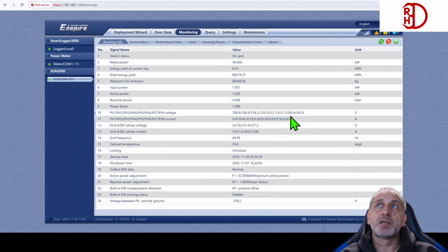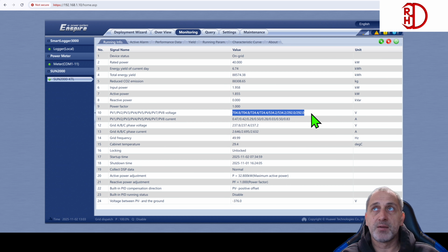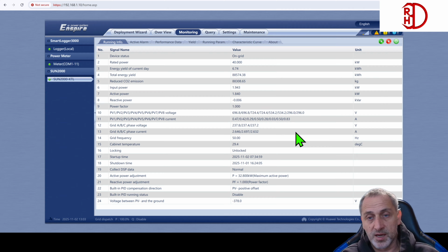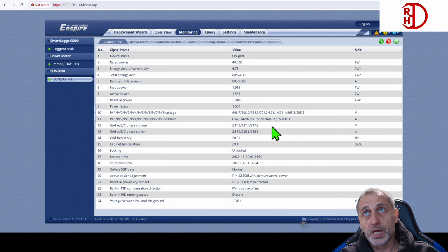So there are many strings, generally 300 volts, the 9 panel strings. This is the special string for now, it's just temporary. It will change to the same, about 300 volts, it will go down, and those big ones are about 750, 800 volts. It is the strings with, let me say, 24 and 23 panels. So this is the system that we are monitoring.